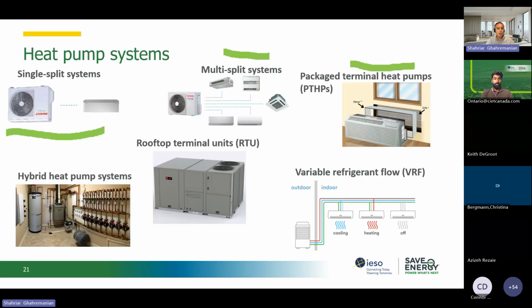The other thing is the rooftop units. These days, if you're ordering a rooftop unit, make sure that you order a rooftop unit with heat pumps, or a heat pump rooftop unit, because as I said, they just need to change one of the little pieces of equipment inside the cycle and convert it to a reversing valve, and then that's it. It becomes a heat pump. So instead of air conditioning, it becomes a heat pump, and if you need a backup, again you can do that. And the cost increase is very minimal if you order heat pumps on these ones.